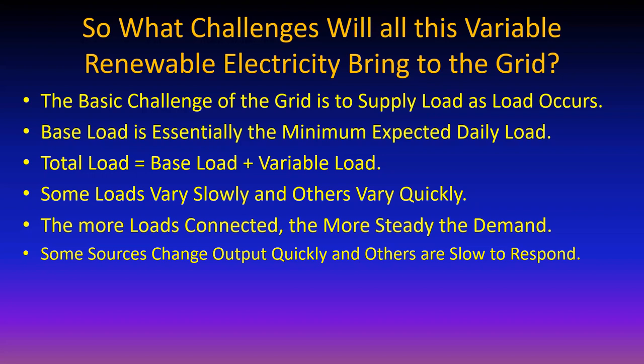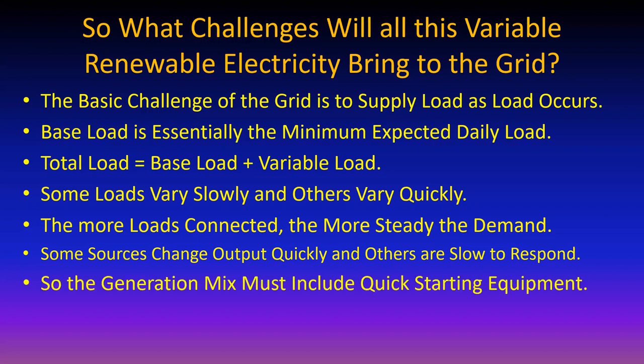But at least they can very quickly bounce back and forth. And yes, as you increase the load, you increase the torque on the machine, and that's what the governor is there for. It applies more fuel to make sure it maintains a constant speed, but it does it quickly. So it's important to know how quickly a source can respond to a change in load, as that's one of its key characterizations.